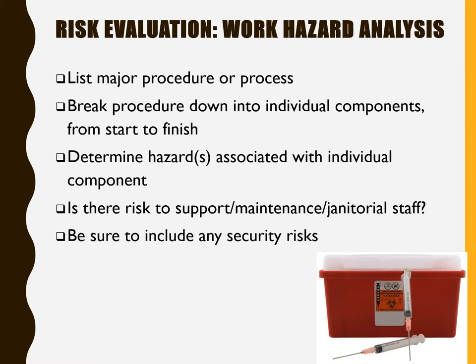Risk evaluation on the basis of the work is done by conducting a protocol-based biohazard risk assessment. List the major procedures or processes and break down each procedure into individual components from start to finish. Determine hazards associated with individual components. Look for any risk to support, maintenance, or janitorial staff, and make sure that all laboratory activities are listed in the protocols.